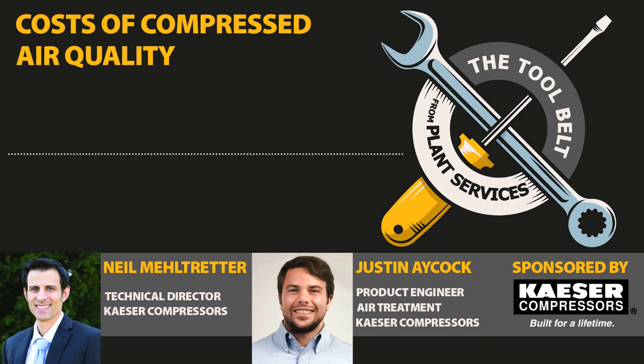Yeah, sure. The material type of the piping can make a difference. Number one, we're always looking at a leak-free system. When we install something, we want to make sure that once it's up and running, pressure tested, holding pressure, that it holds pressure indefinitely.